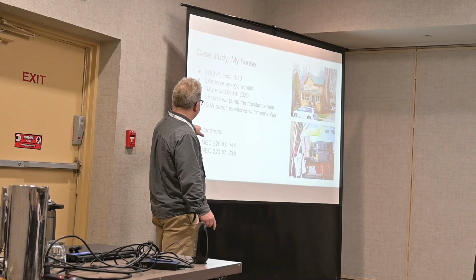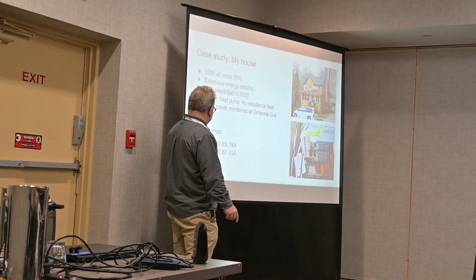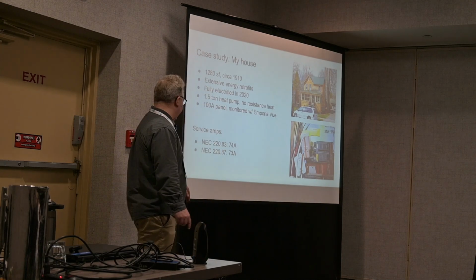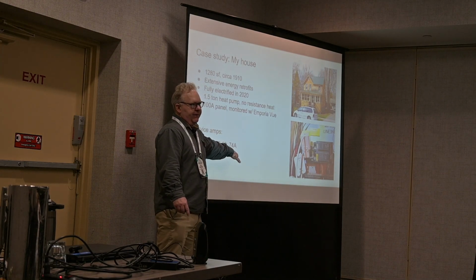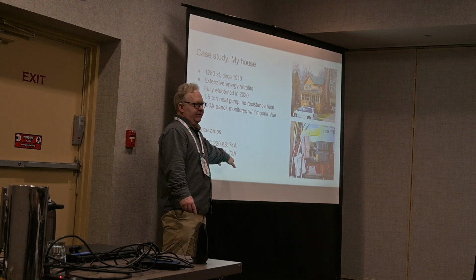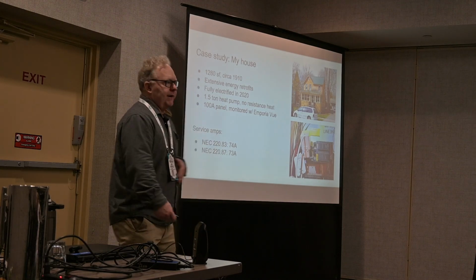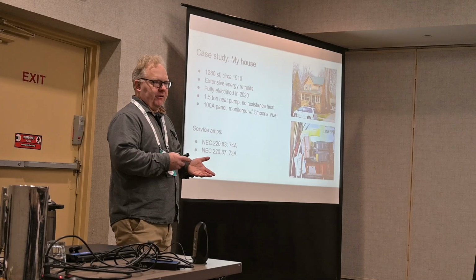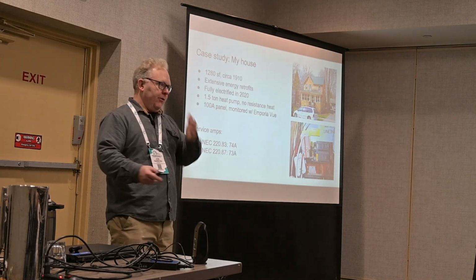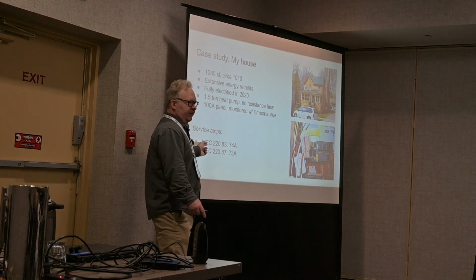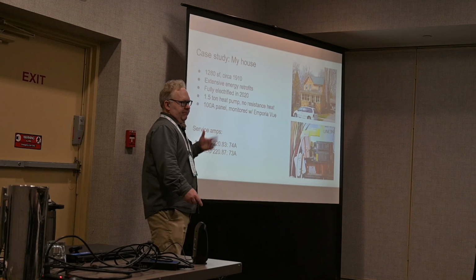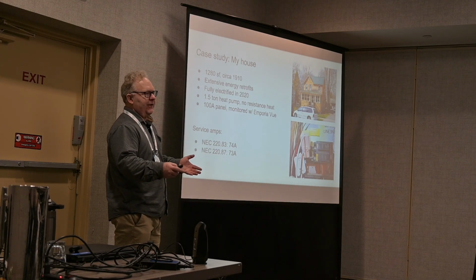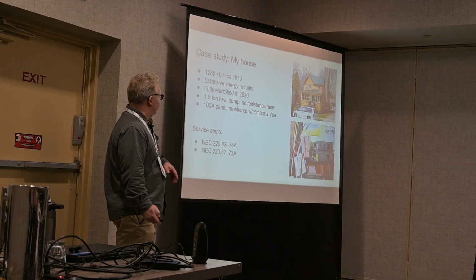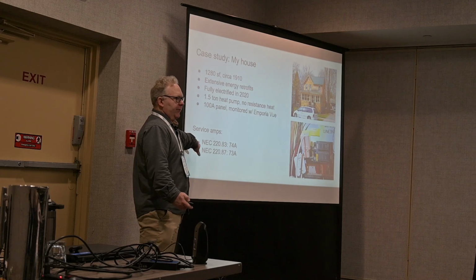And I did these load calculations based on the house as is, or in its current electrified state. When I did the spreadsheet clipboard calculations, I got 74 amps. When I did it based on my measured data from the Emporia, it came in at 73 amps. I think it was somewhat good fortune that these results came out so similar. My impression is that overall the clipboard method tends to be a little more conservative, and that the monitor data, because it actually sees how you're using the house, can give you a little more room to work with the panel.